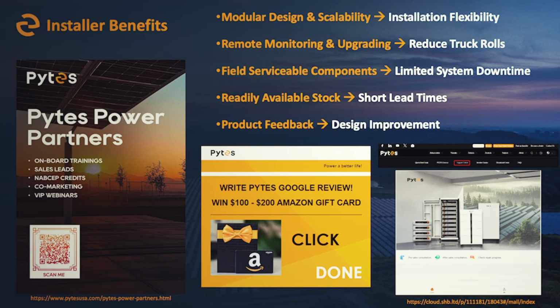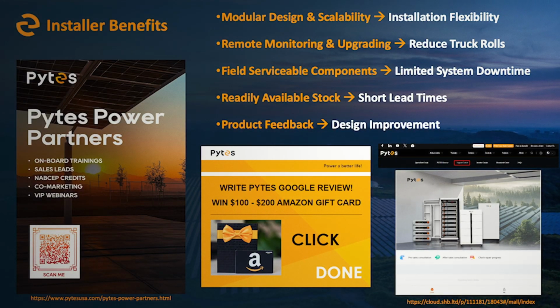I think we need the serial number from the Wi-Fi stick, and then you just need to confirm that the Wi-Fi dongle is connected to the internet. And then the third thing, which is really important, is you want to make sure the batteries are in an idle state. We don't want the batteries actively charging or discharging, because when we do these updates, and it's the same for on-site updates with the laptop, the updates reset the BMS and the battery itself resets. So we want the batteries to be in an idle state, meaning you disconnect the inverter or put your system in AC bypass mode, let the genny cover the loads, and make sure the batteries are just in standby.